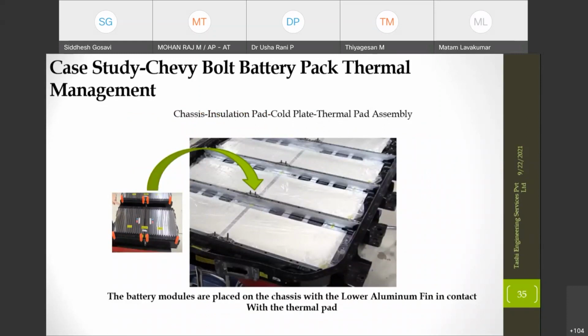If I consider it as a sandwich layer: there will be the cell, below it the thermal pad, below that the cold plate, below the cold plate the insulation, and below the insulation the battery casing. This is the pathway for the complete heat transfer process, and this pathway should have as minimum resistance as possible.